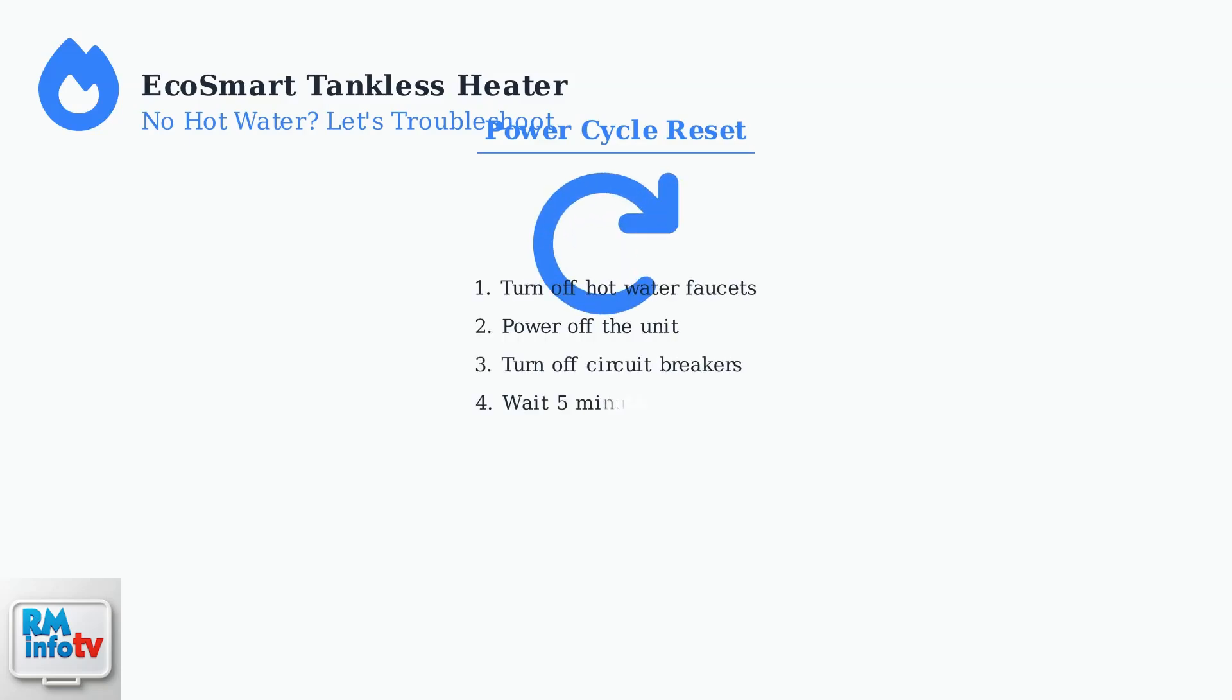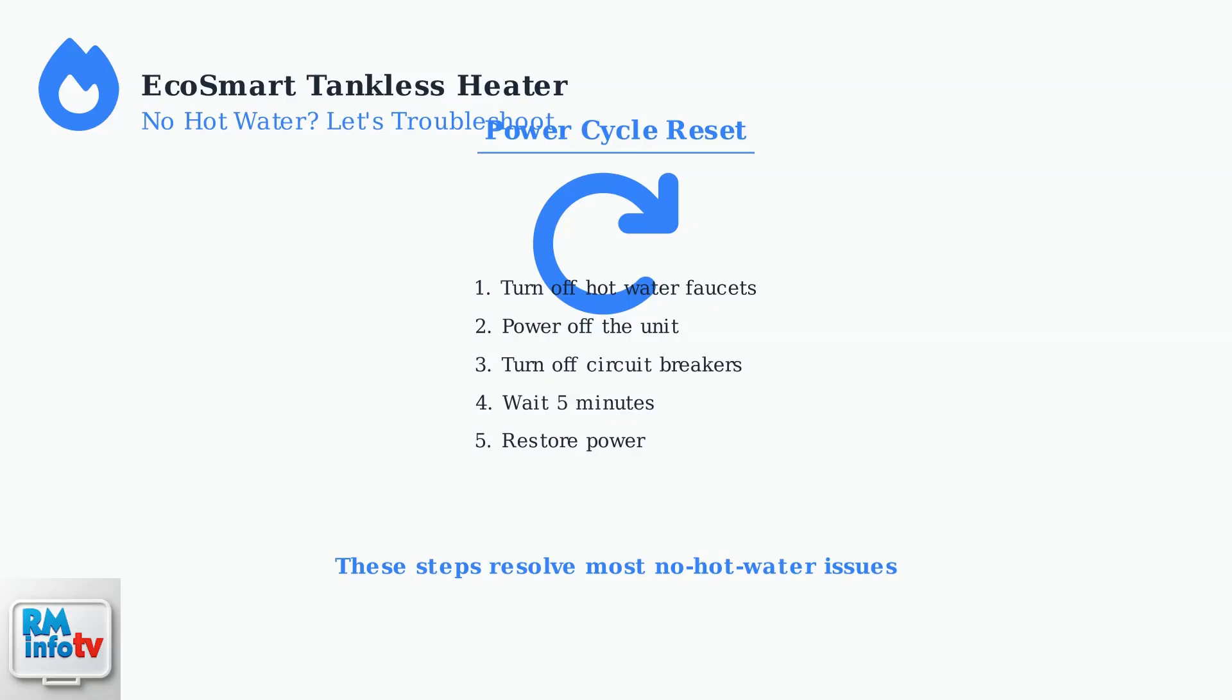Finally, try a power cycle reset. Turn off all hot water faucets, power off the unit, turn off the circuit breakers, wait five minutes, then restore power. This simple reset can resolve many transient issues.